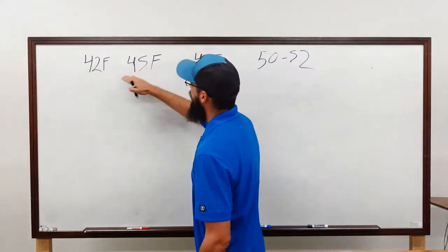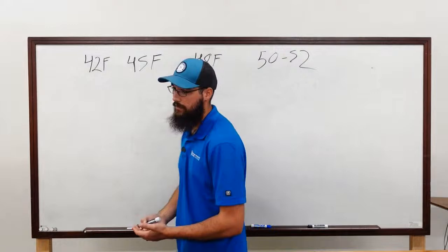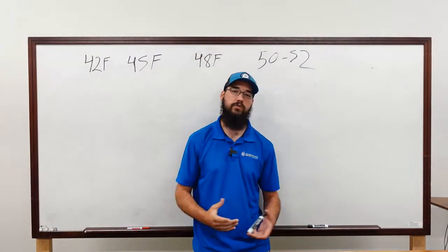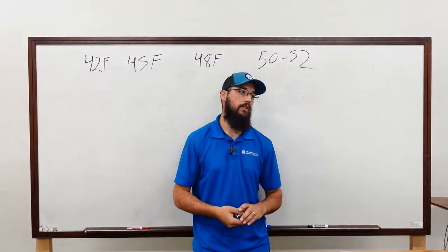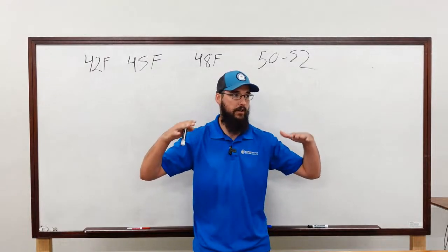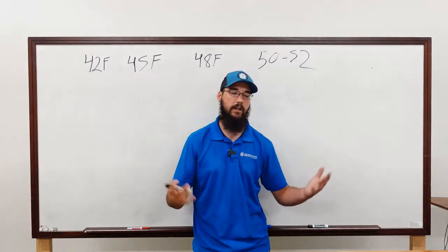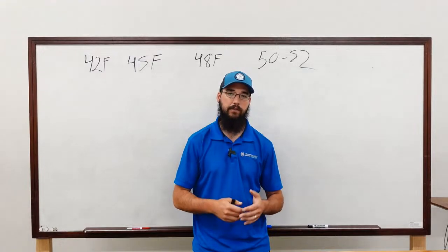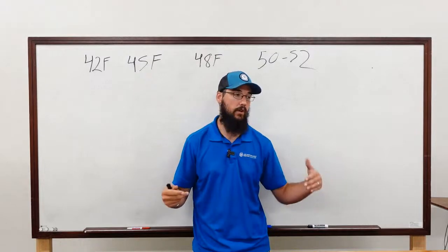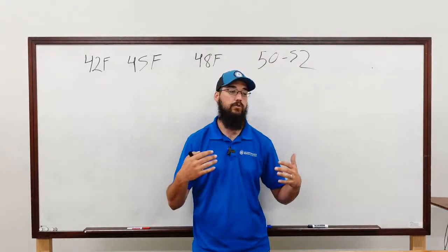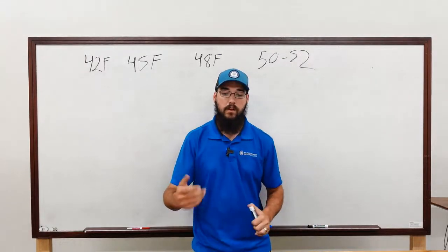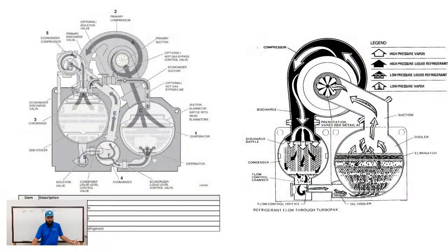So, okay, we've got this. When we think about a regular air conditioning scenario, we talked pretty heavily about how we can load control in the air-cooled class. If we've got a scroll machine, scroll machines are pretty straightforward. They have loading and unloading ability in digital scrolls, and they are putting them on variable speed drives now. But typically, the most common way is they turn off and on. As you need more or need less, it's a very inefficient way of doing it, but it is one way to do it.